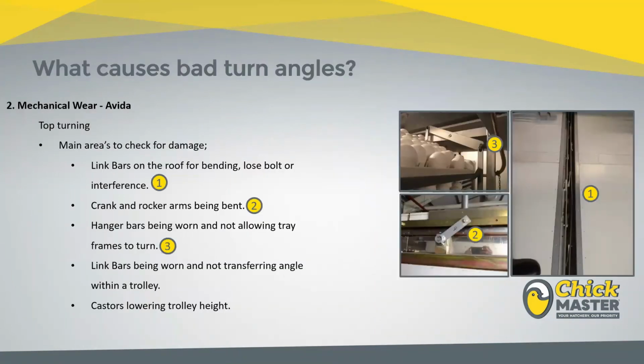Now, once you've got the configuration correct on an Avida, that system's going to run absolutely fine for a decade or more. However, as with the Classic, you can have an amount of mechanical wear that you're going to have to rectify eventually. This usually comes around in these machines around 8 to 10 years, depending on how well the machine's been maintained. The first thing you want to look out for, and you don't want to have to wait 10 years to do this, I'd recommend doing it at least annually, is you want to check all of the link bars for any damage. So this is the link bars and the crank bars.